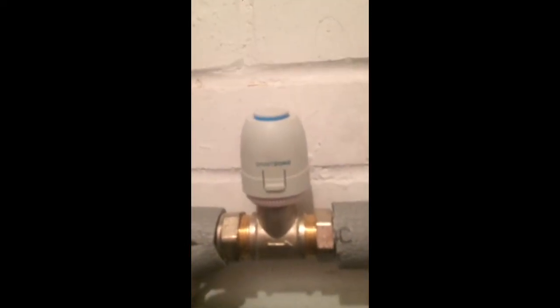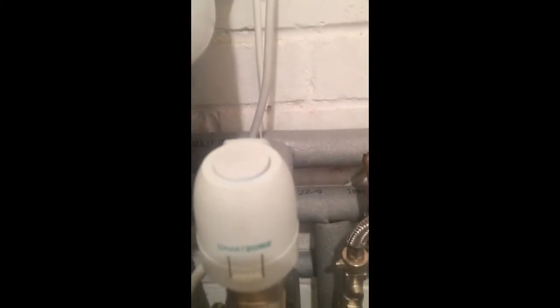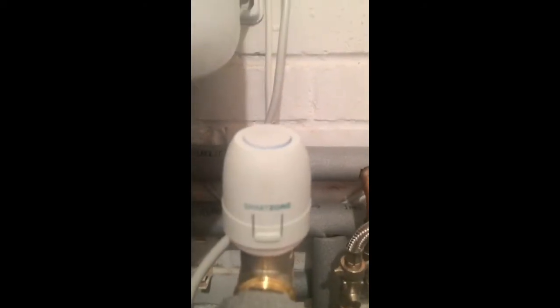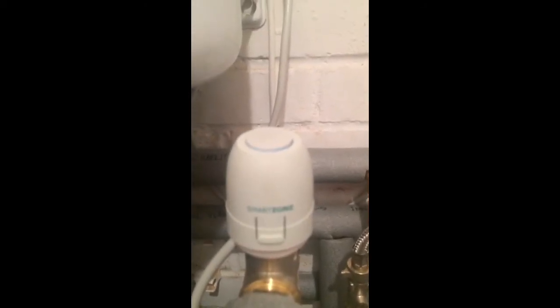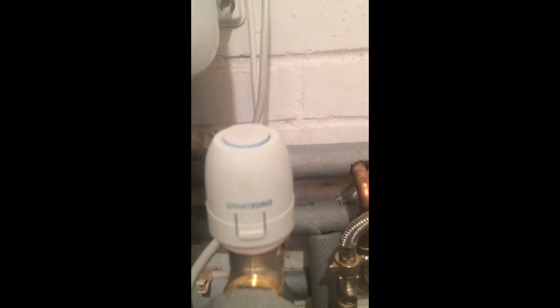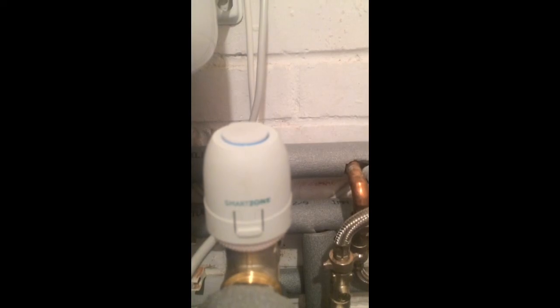That one's slowly going down now and the light will slowly start to come up. It takes around 90 seconds to two minutes for the valve to fully come up and down. It's just starting to go blue now — valve's coming up, and that one's slowly closing. And that's the new Smart Zone two-port valve. I'm impressed, so I'll be using these again hopefully. Thanks for watching. Take care.